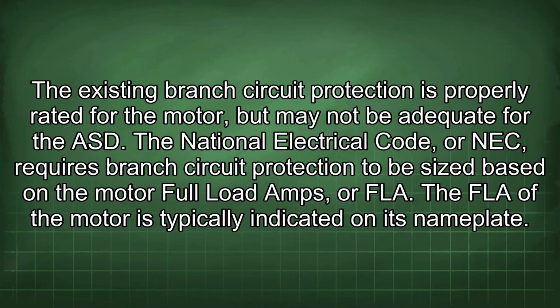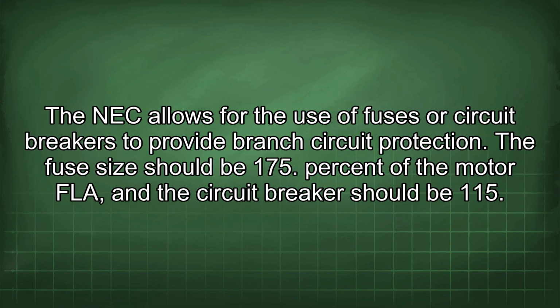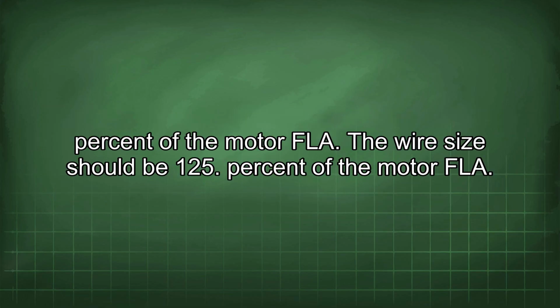The existing branch circuit protection is properly rated for the motor but may not be adequate for the ASD. The National Electrical Code, or NEC, requires branch circuit protection to be sized based on the motor full load amps, or FLA. The FLA of the motor is typically indicated on its nameplate. The NEC allows for the use of fuses or circuit breakers to provide branch circuit protection. The fuse size should be 175% of the motor FLA, and the circuit breaker should be 115% of the motor FLA.